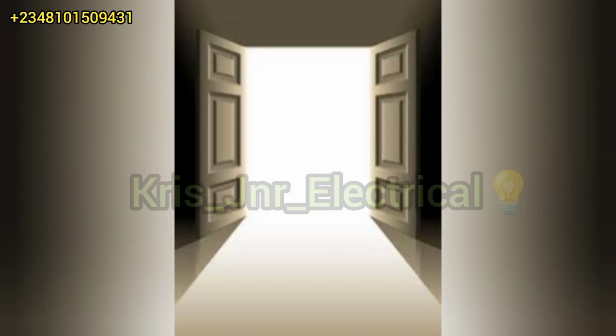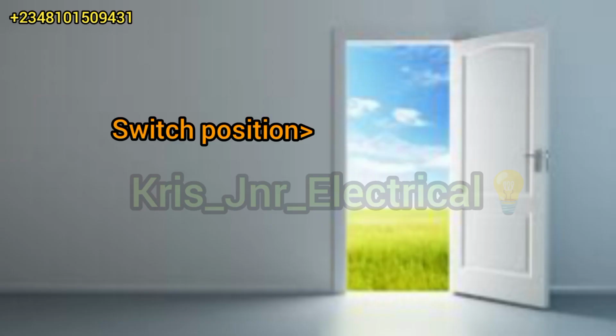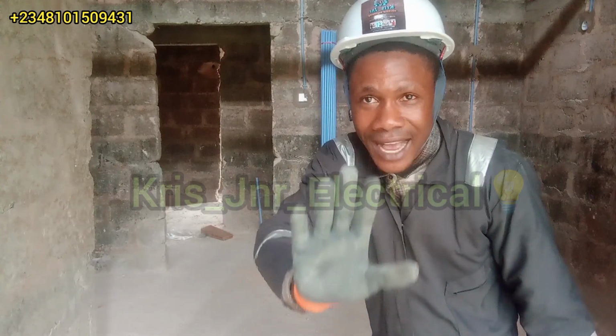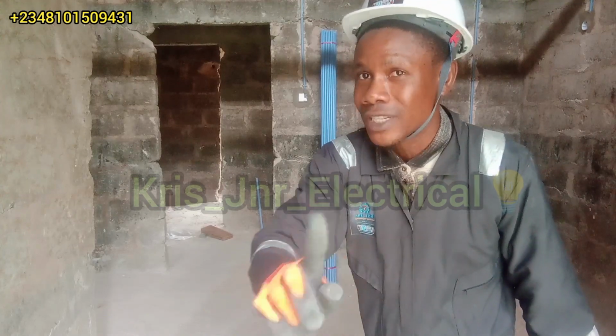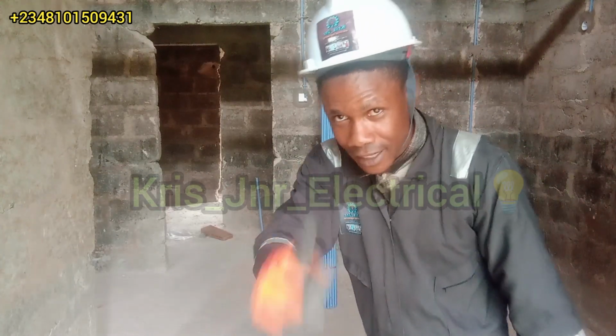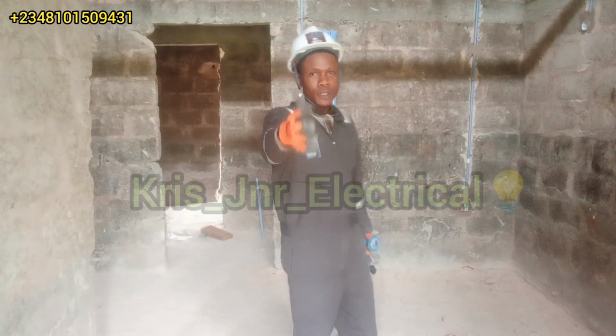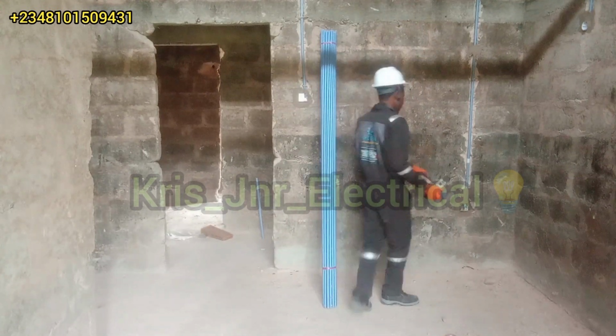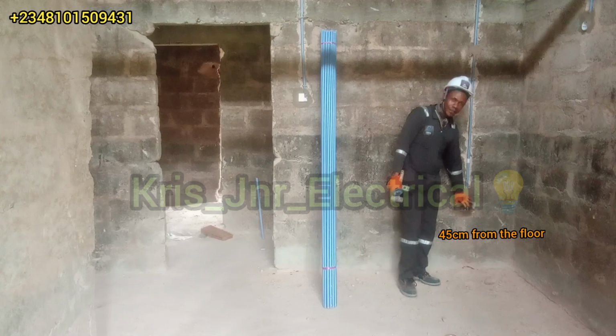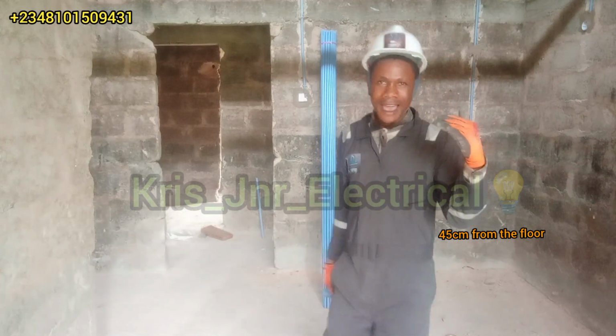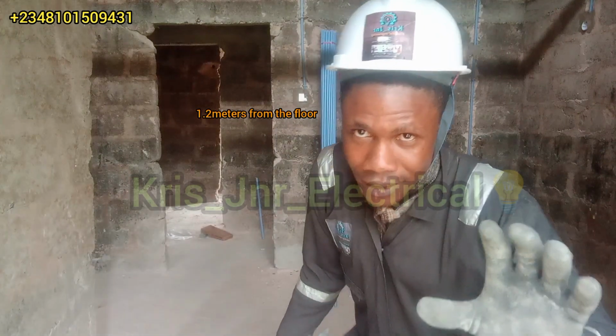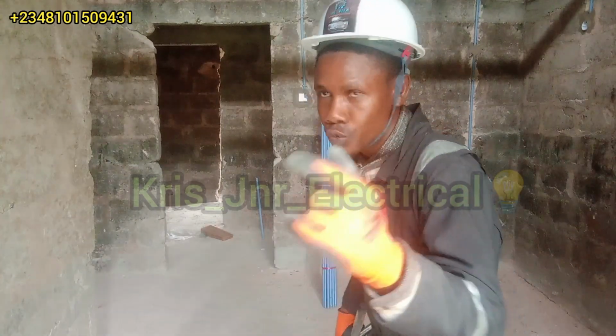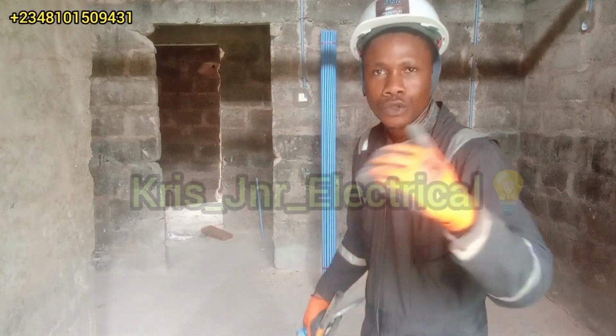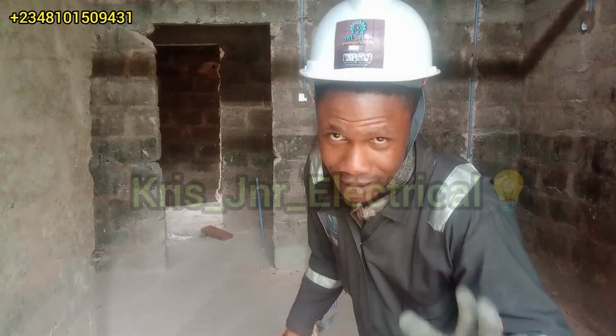So you must make sure that your switch is about 1,200 millimeter from the floor level. That is the position of the switch as prescribed by the IEE Regulation 18th edition. And for your socket, you must make sure it is 45 centimeter from the floor. This is the position of the socket here. The minimum height of a socket is 45 centimeter, and the maximum height of your switch should be 1,200 millimeter. Do you understand that?